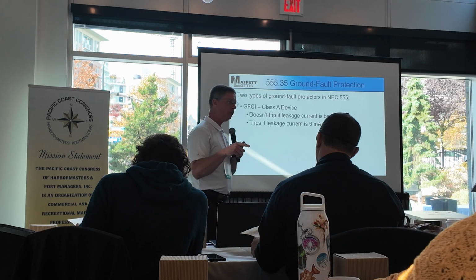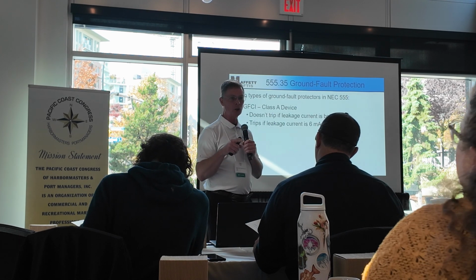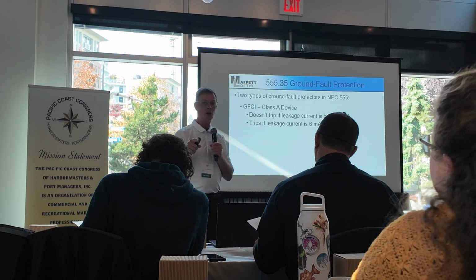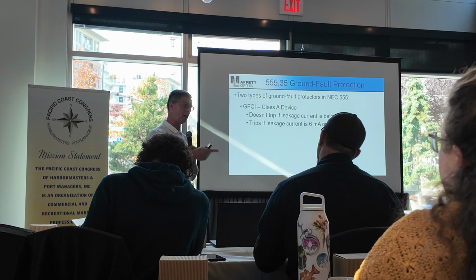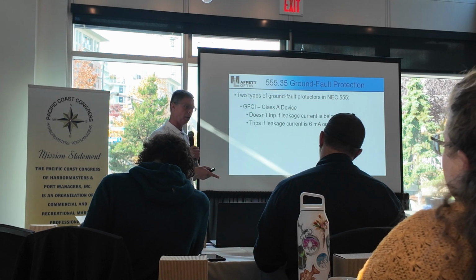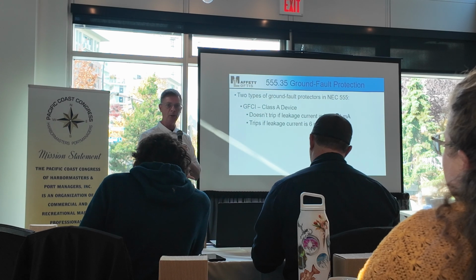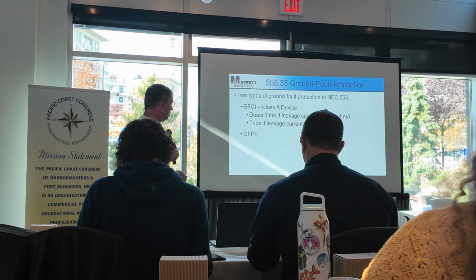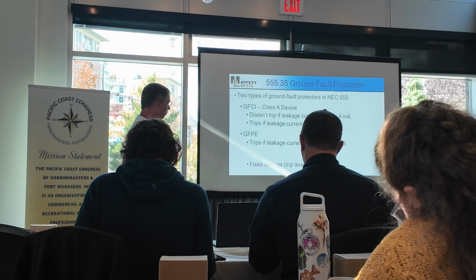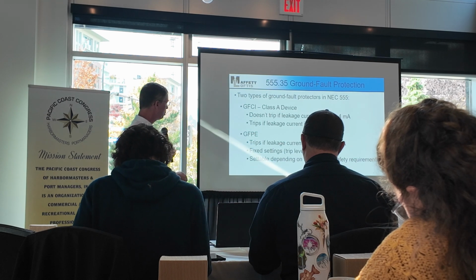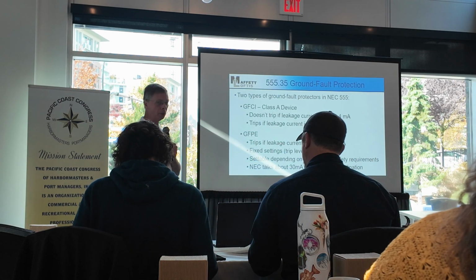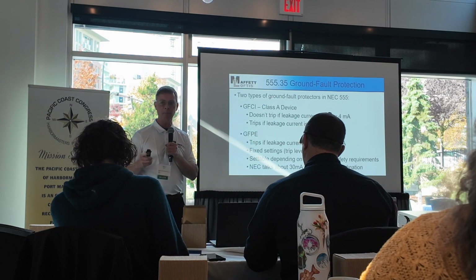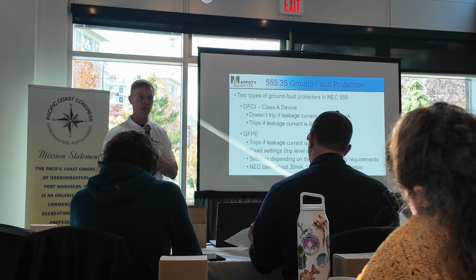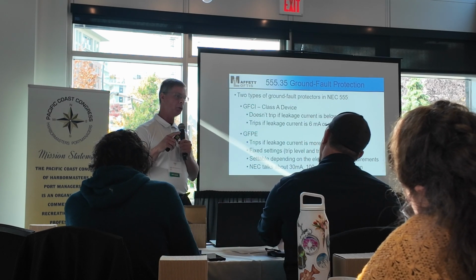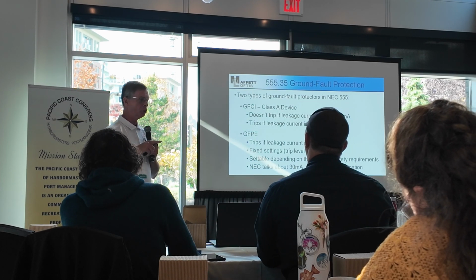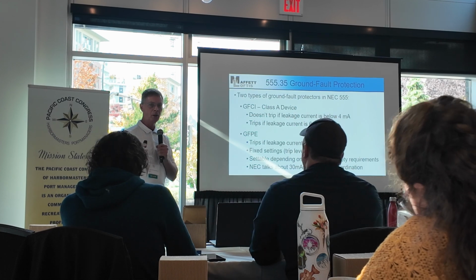And do not get that confused with the GFPE, because contractors have installed a GFCI where I designed a GFPE. It's two different entities. A GFPE is anything that really trips above 6, and in the marina world, we have two settings, which is the 30 and 100. So the 30 and 100 are GFPE, ground fault protection of equipment. The GFCI is ground fault circuit interrupter. So there's two different devices.